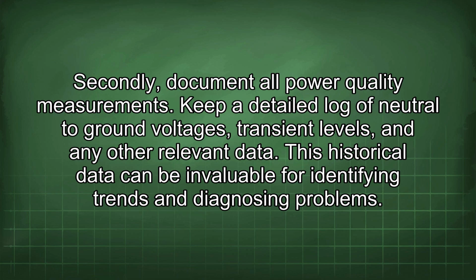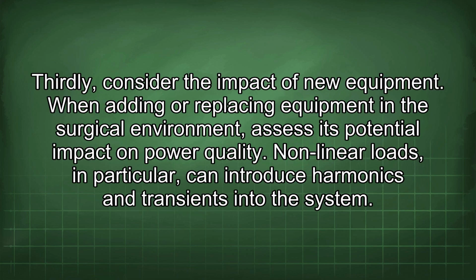Secondly, document all power quality measurements. Keep a detailed log of neutral to ground voltages, transient levels, and any other relevant data. This historical data can be invaluable for identifying trends and diagnosing problems. Thirdly, consider the impact of new equipment. When adding or replacing equipment in the surgical environment, assess its potential impact on power quality. Nonlinear loads, in particular, can introduce harmonics and transients into the system.